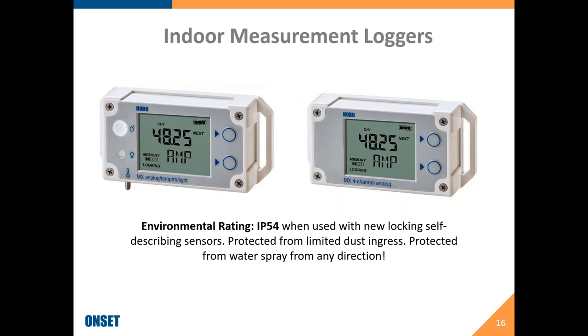These are two of our newest Bluetooth indoor data loggers. They do have an environmental rating of IP54, which means they are protected from limited dust ingress — more robust in an environmental or industrial type application, even if they're getting a bit sprayed down. These can accommodate temperature relative humidity light sensors, AC current, AC amperage, additional temperature sensors, and temperature sensors that could be put on a pipe for the supply and return on equipment.